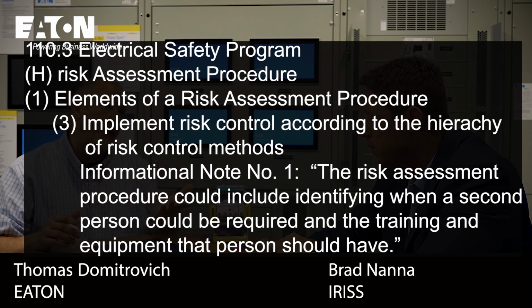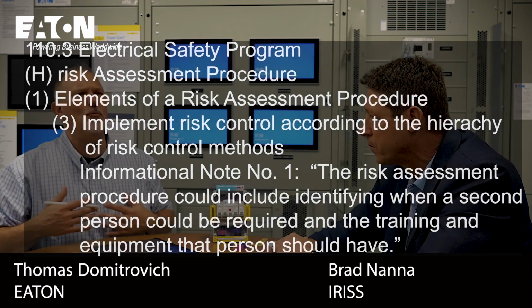When you actually get everything exposed and you're doing the thermography, you're not in there with your elbows in it, you're standing outside. So from a risk perspective, looking at likelihood and severity, the severity is high, you could be... it always depends on the amount of incident energy.